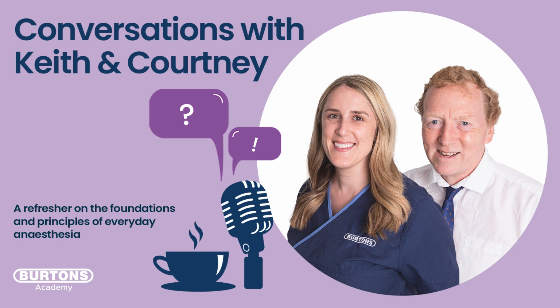And we do the same thing in reverse when we want to use that arterial line for blood sampling. I know we're not up to that bit, but just while I'm quickly visualizing, if we want to take an arterial blood gas sample from our art line, from our transducer, without having to shuffle under the drapes, you just shut off port 3 o'clock so that you open up from the patient, port 9 o'clock, to where you're going to stick your syringe, port 12 o'clock. And then you just draw back on your syringe and get your blood sample and away you go.